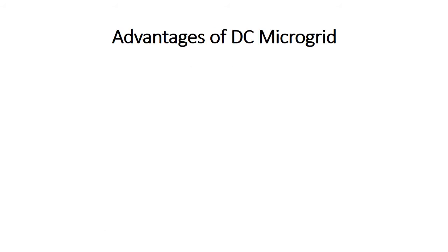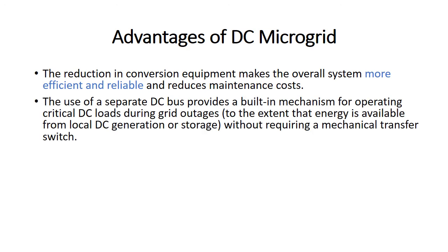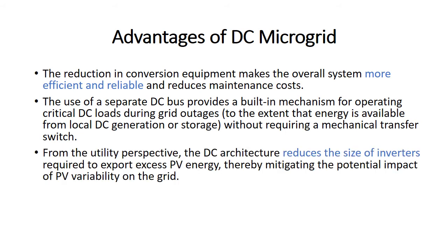Advantages of DC microgrid: first, the reduction in conversion equipment makes the overall system more efficient and reliable and reduces maintenance cost. The use of a separate DC bus provides a built-in mechanism for operating critical DC loads during grid outages without requiring a mechanical transfer switch. From the utility perspective, the DC architecture reduces the size of inverters required to export excess PV energy, thereby mitigating the potential impact of PV variability on the grid.